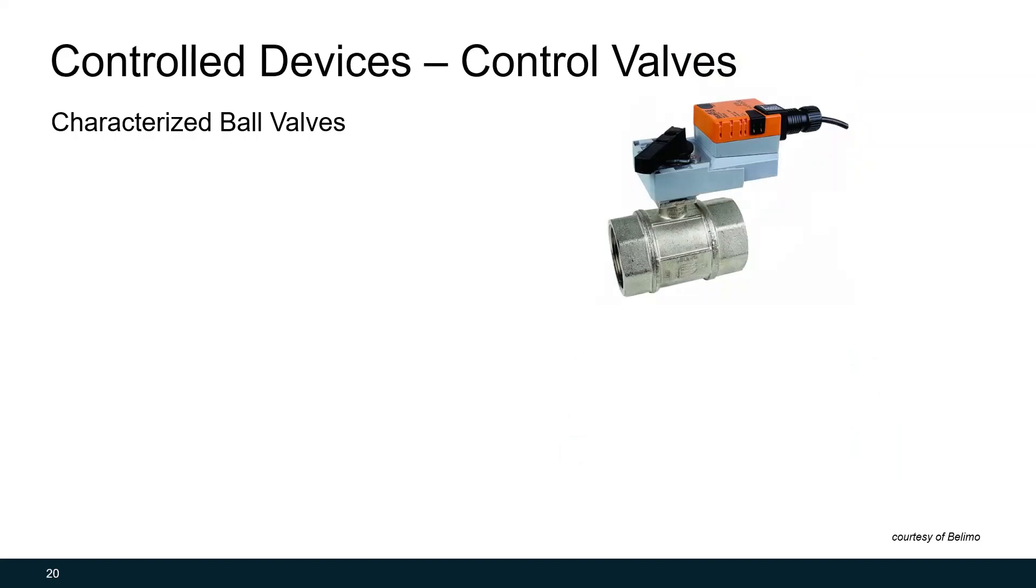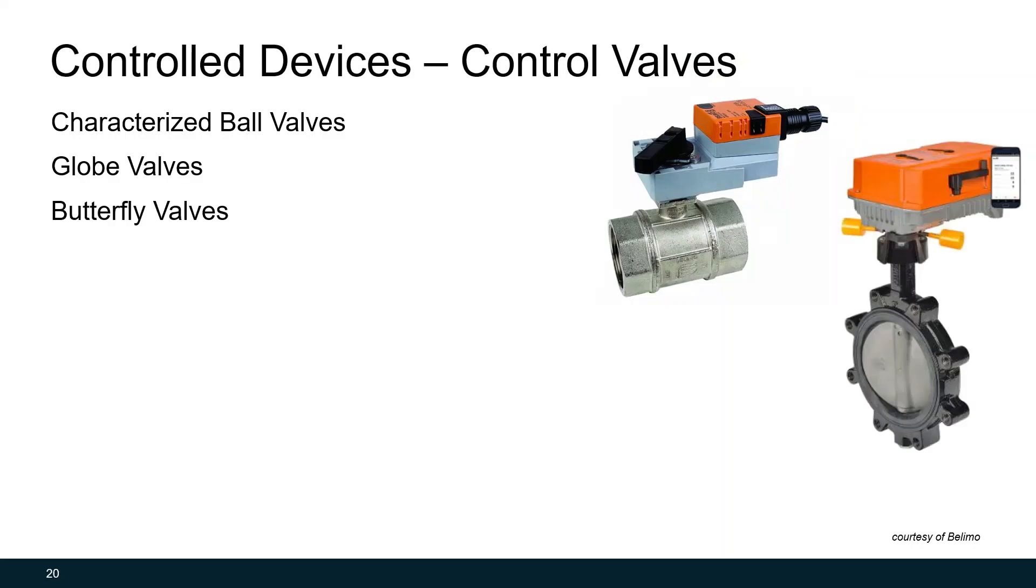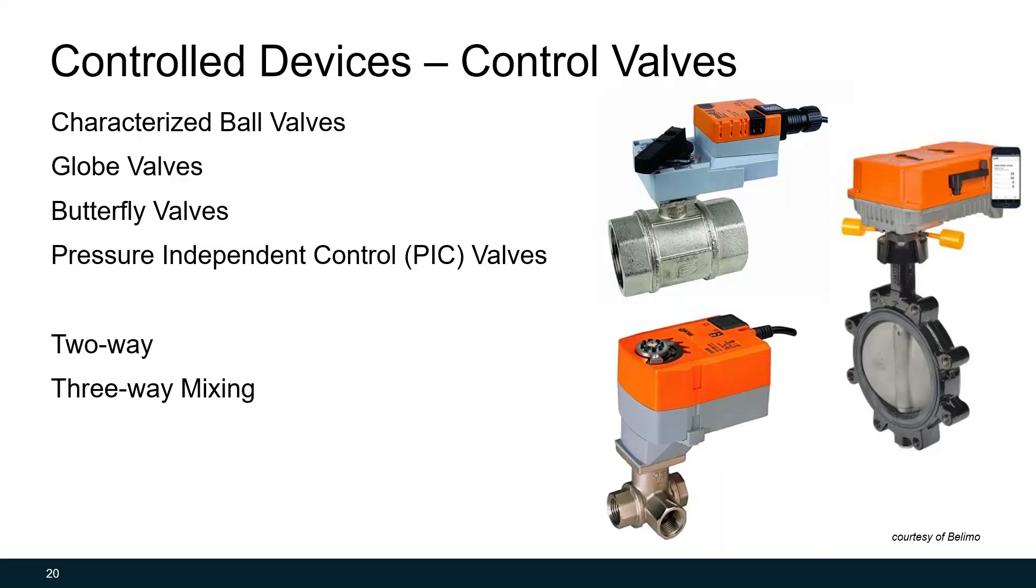Then there's control valves. There's many types of control valves, but most typically we use characterized ball valves for valves that are two inches and less. For four inches and less, you start to see globe valves. And for anything larger than that, you start to see larger butterfly valves. Another alternative for small pipe valves are pressure independent control valves. These valves are self-balancing and remove the cost for adding a separate balancing valve. The valves pictured here are two-way valves, but you can also get three-way valves. Three-way valves can be mixing or diverting. Mixing valves is where you are mixing two different fluid streams, whereas with diverting valves, you are picking between two different fluid flow paths.